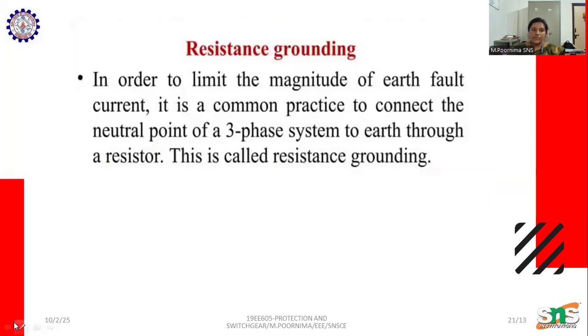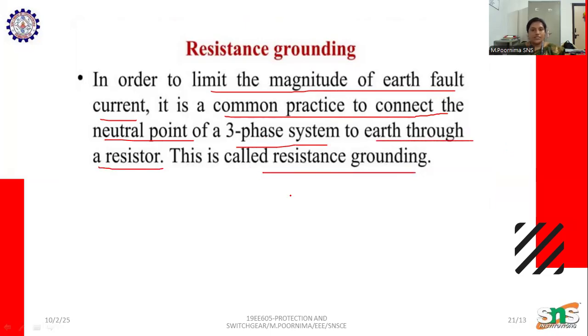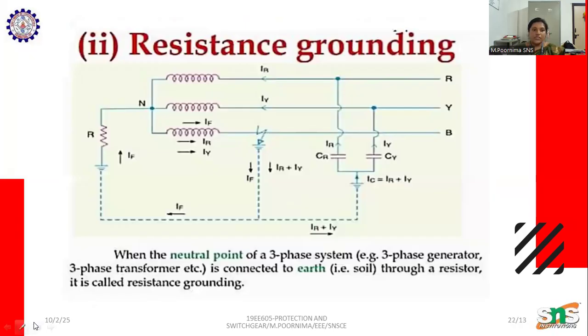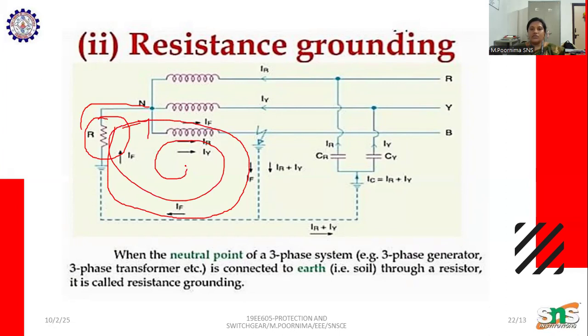The next type is resistance grounding. In order to limit the magnitude of the earth fault current, it is common practice to connect the neutral point of a three-phase system to the earth through a resistor. It is called resistance grounding. Here we can see the diagram and the difference. In the previous one, the neutral was directly grounded. Now the neutral is grounded through a resistor. The same process takes place, but this limits the magnitude of the current.